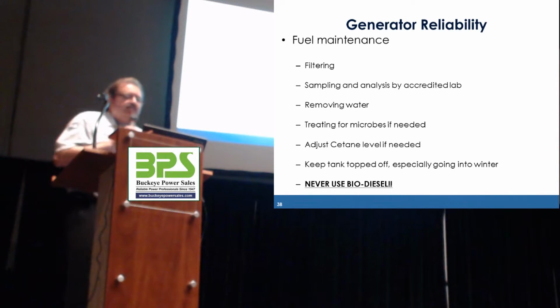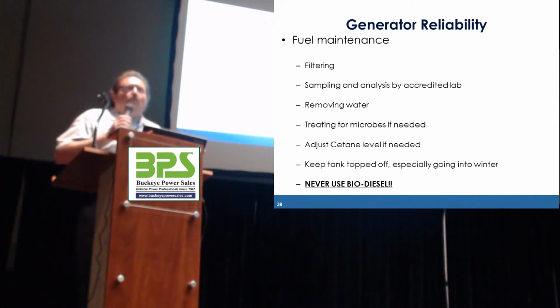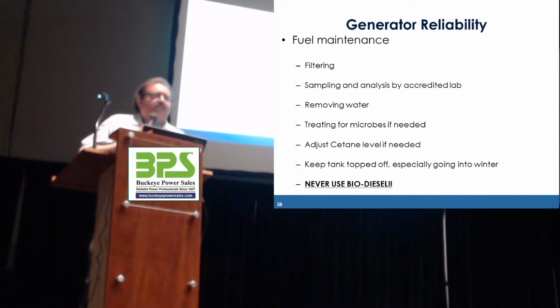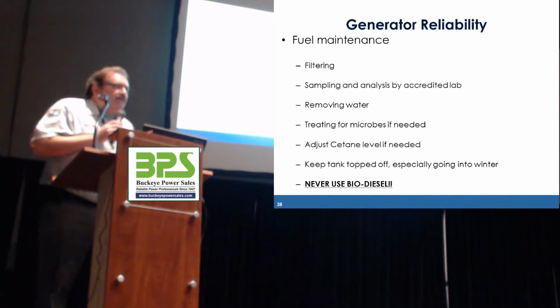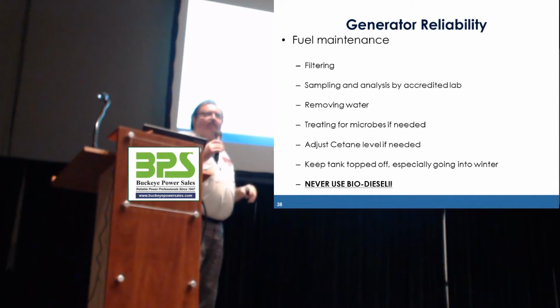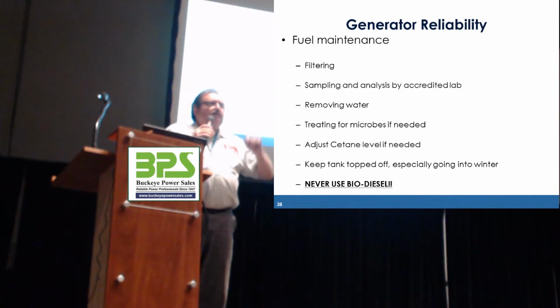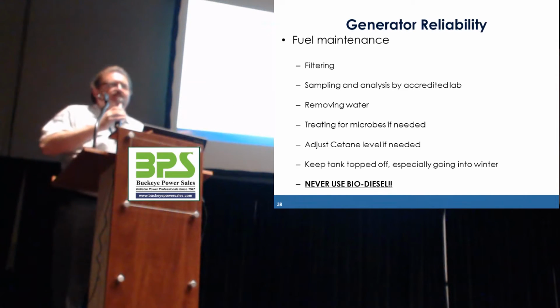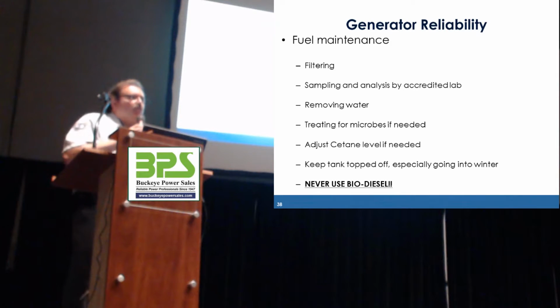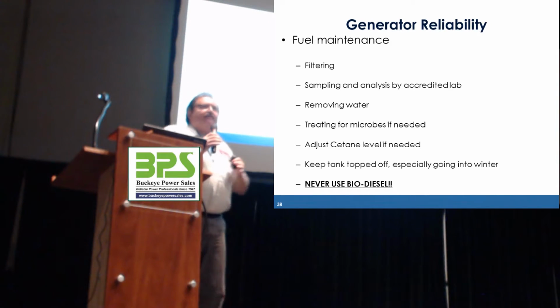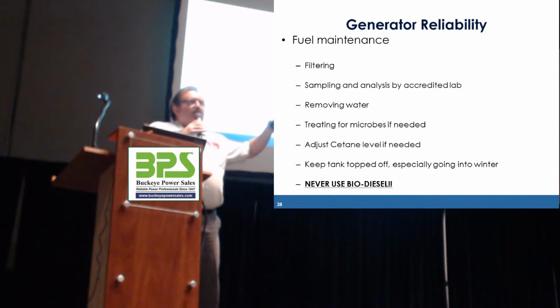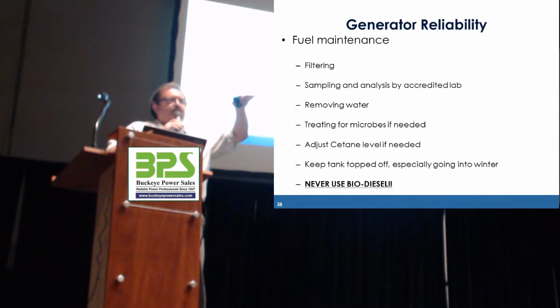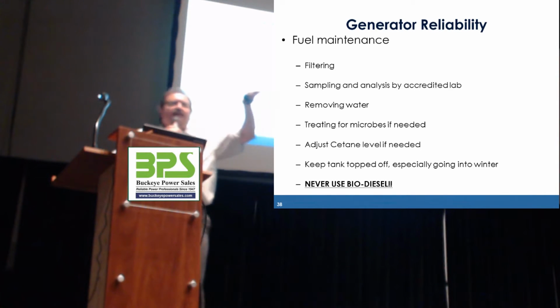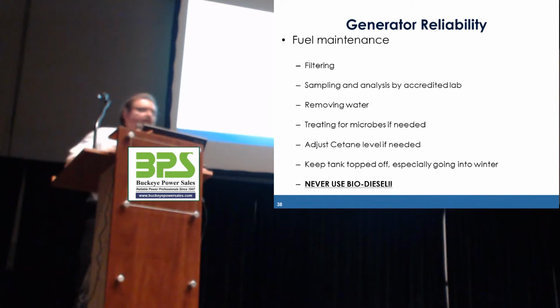Now, one of the biggest causes of microbe growth is water. They can't live in the fuel itself. They live in the water. And one of the biggest causes of water in the fuel is not necessarily the delivery truck. It's when the tank is not close to full, and you can't fill it completely full. But diesel fuel really expands and contracts with the outside temperature. So what happens is when it gets really warm out, the fuel expands, and then when it gets cold, the fuel may have been touching the top of the tank, and it condenses as it cools.